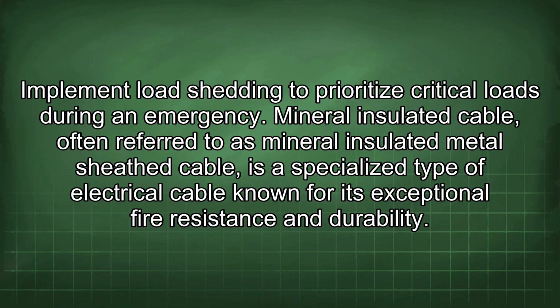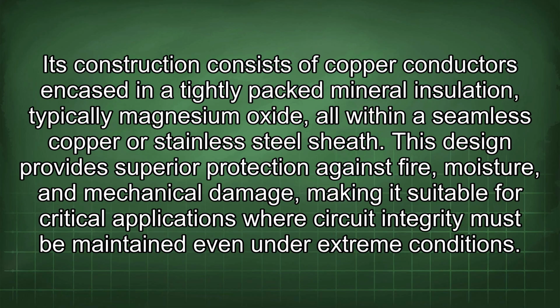Mineral-insulated cable, often referred to as mineral-insulated metal sheath cable, is a specialized type of electrical cable known for its exceptional fire resistance and durability. Its construction consists of copper conductors encased in a tightly packed mineral insulation, typically magnesium oxide, all within a seamless copper or stainless steel sheath. This design provides superior protection against fire, moisture, and mechanical damage, making it suitable for critical applications where circuit integrity must be maintained even under extreme conditions.